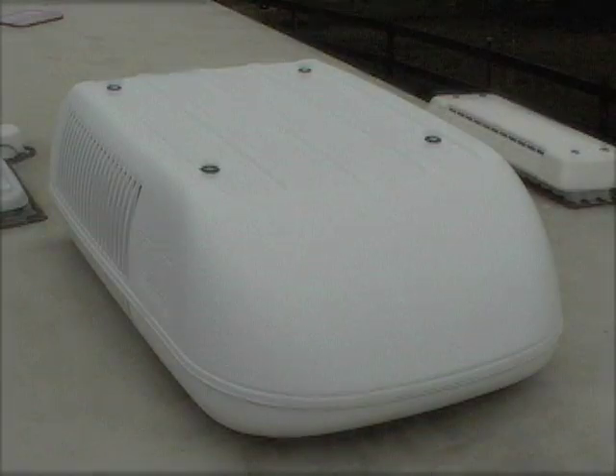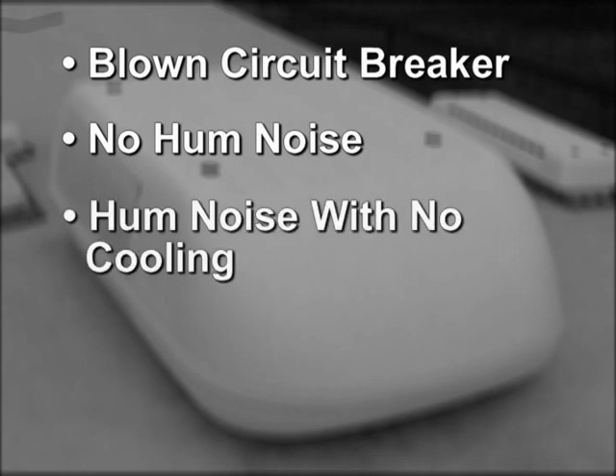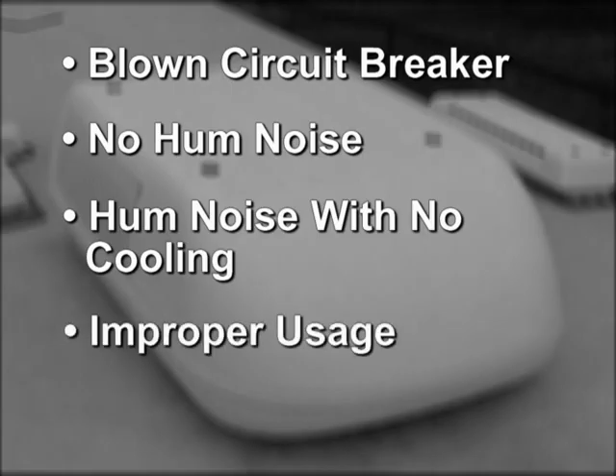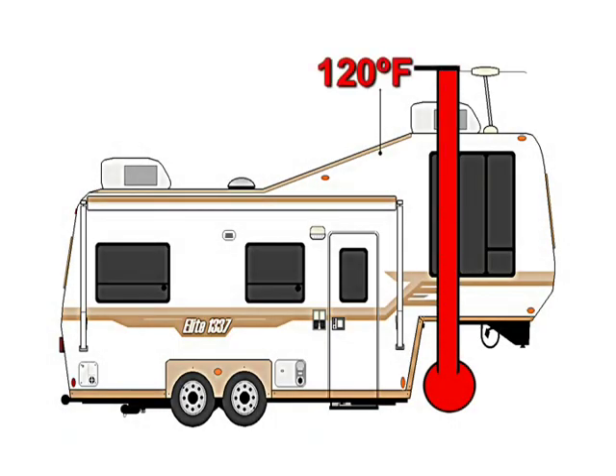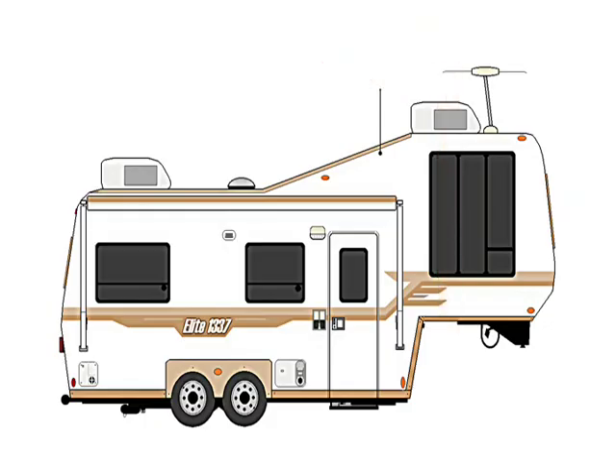The 4 most common problems I see with air conditioners are a blown circuit breaker, usually an easy fix, no hum, telling me that there is likely a control or a compressor problem, a hum and no cooling, telling me there is probably trouble in the air conditioner itself, or improper usage. I've seen people go golfing for the day, and come back and their unit is 120 degrees inside, and they expect the air conditioner to give them immediate relief. This is not realistic.